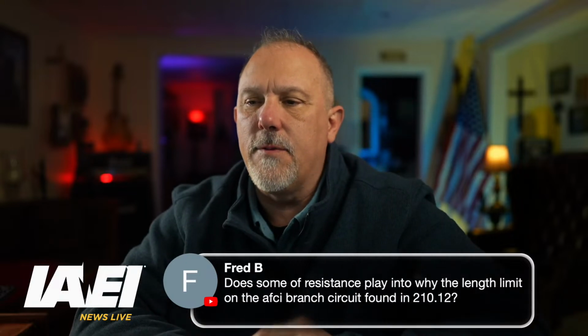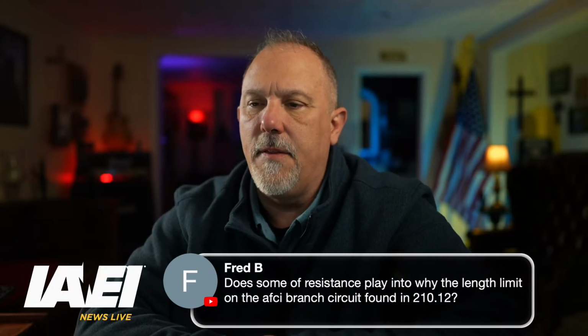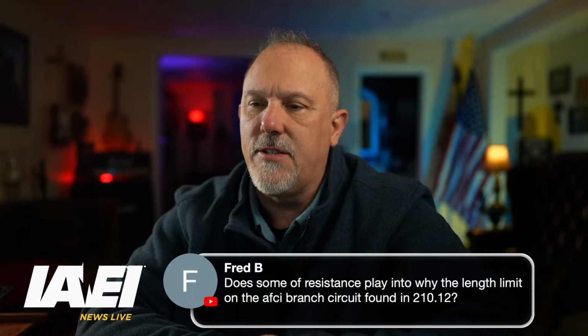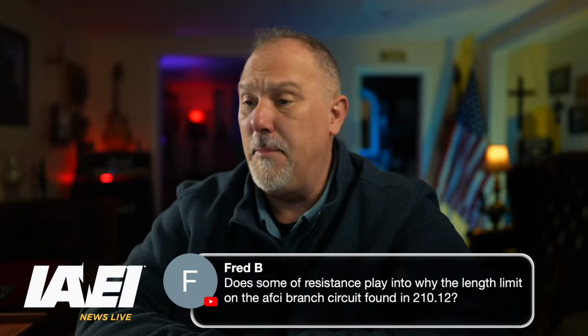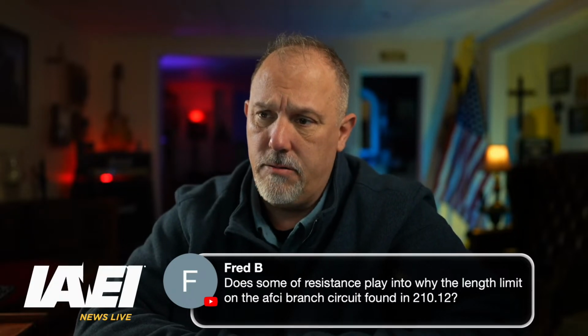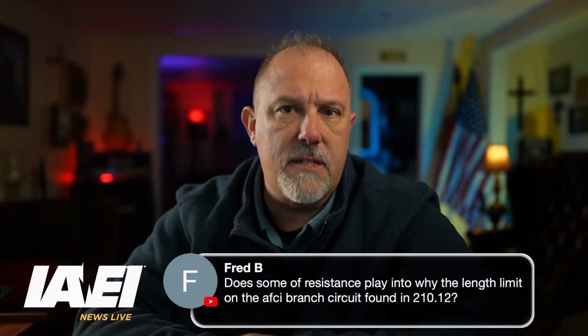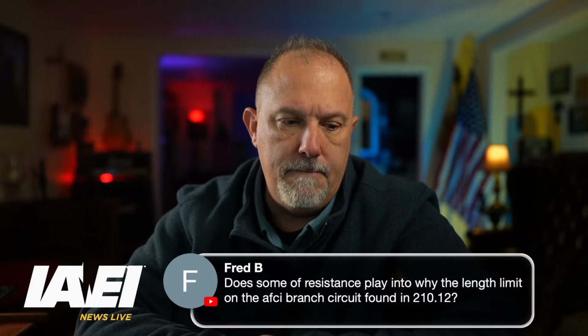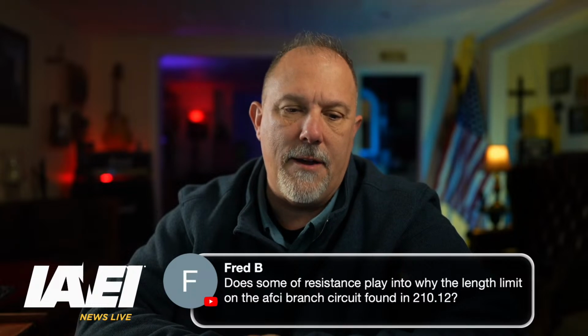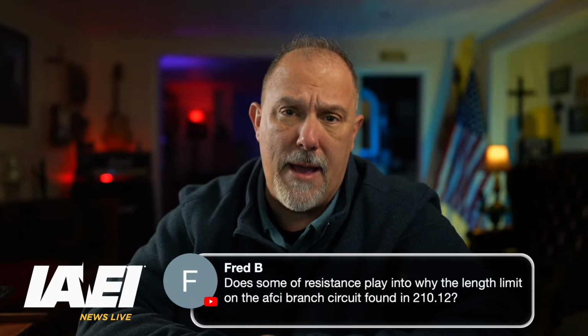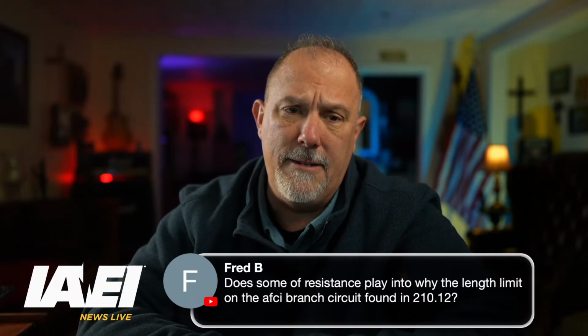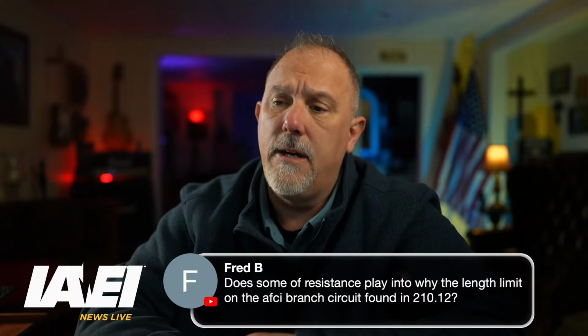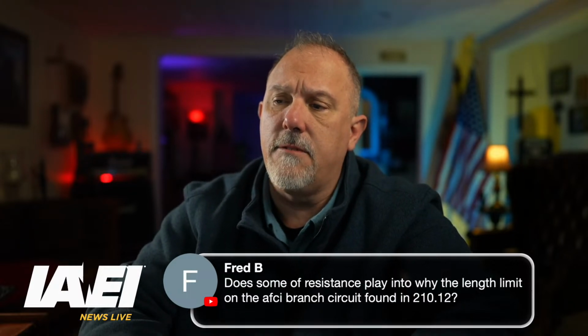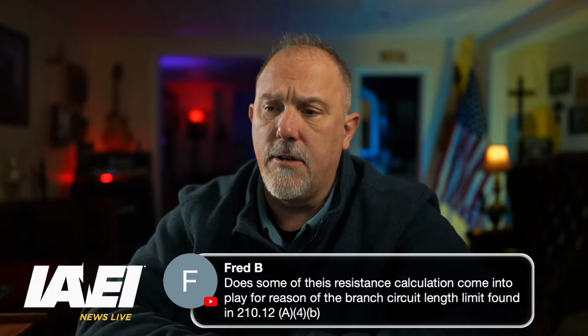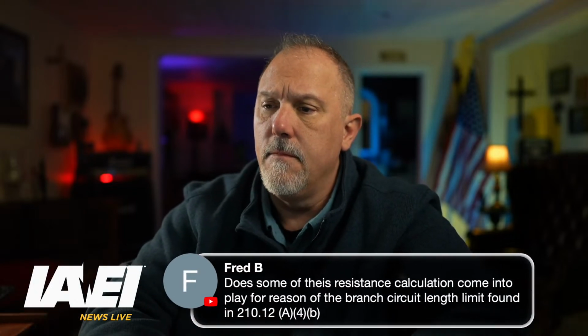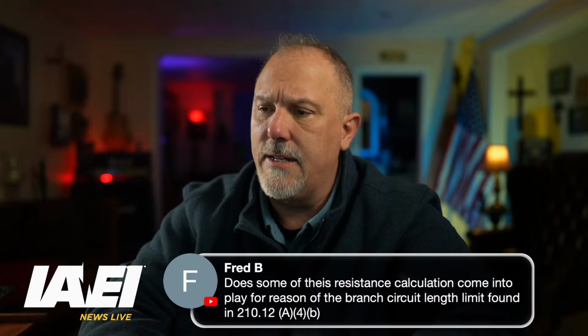Does sum of resistance play into why the length limit on the AFCI branch circuit found in 210.12? Freddie B. The length is about the impedance of that circuit. Don't even get me started on how that calculation, because the calculation doesn't match the research that was done. But yes, it's the resistance and reactance of the conductor length. The circuit lengths, yes.